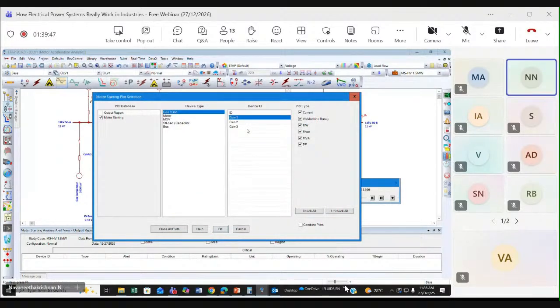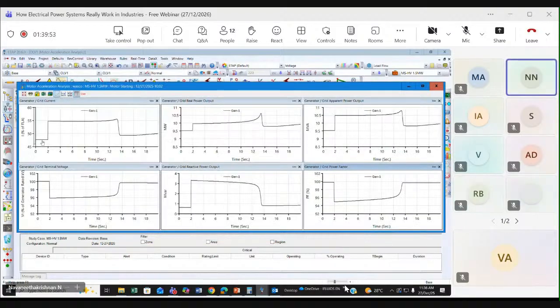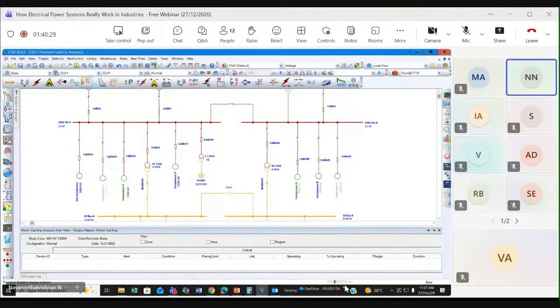Generator. You can see the graph of how the generator voltage behaves here. The full load amps of the generator rises because of the motor starting current. But what happened? The AVR will compensate during this period. In motor starting, you check whether the motor is starting and whether your generator is capable of starting it or not. This is 96%. Stability also, how we did it, because of time I'm rushing through.